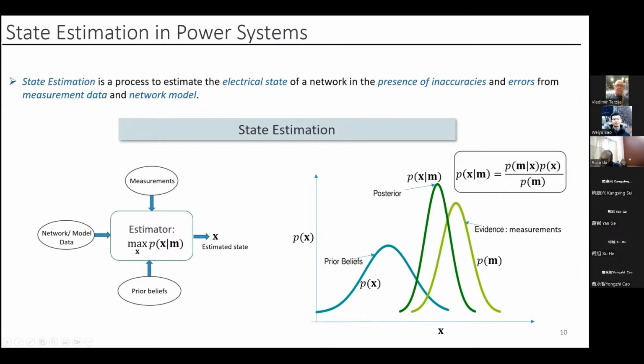However, if we have a very strong prior belief, gathered from enough prior data, we can compensate for the lack of measurements. This is what a distribution state estimator typically tries to achieve: it compensates for the lack of measuring devices in the distribution system using some prior belief about the evolution of the system states. Otherwise, we are always in an unobservable scenario for a distribution network. So the prior belief plays a key role in estimating the states of a distribution system.